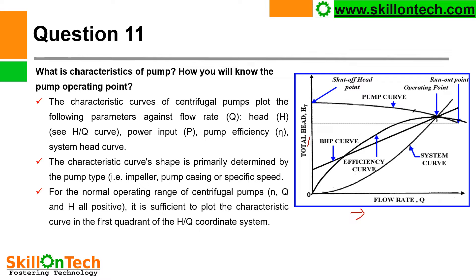Power input — this is the BHP curve. Pump efficiency — this is the pump efficiency curve. And this is the system head curve, which shows the resistance of the system against fluid flow. The characteristic curve shape is primarily determined by the pump type, impeller, pump casing, or specific speed. For the normal operating range of a centrifugal pump, N, efficiency, flow, and head are all positive, so it is sufficient to plot the characteristic curve in the first quadrant of the HQ coordinate system.